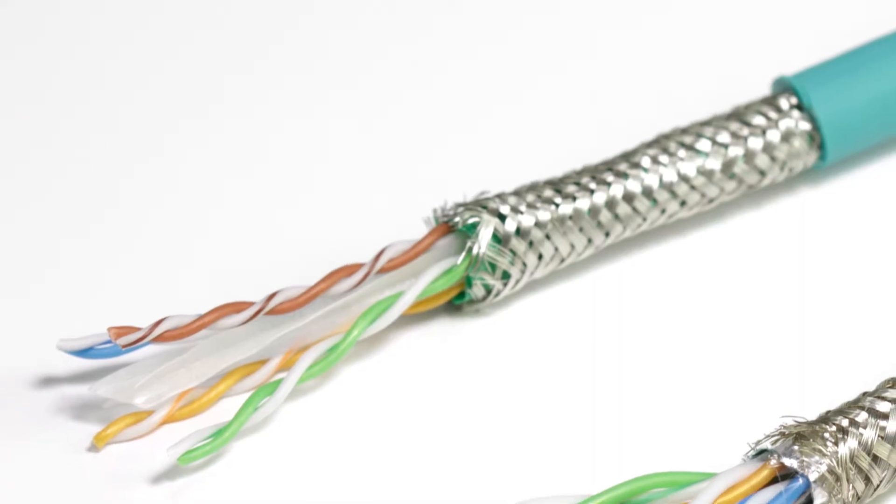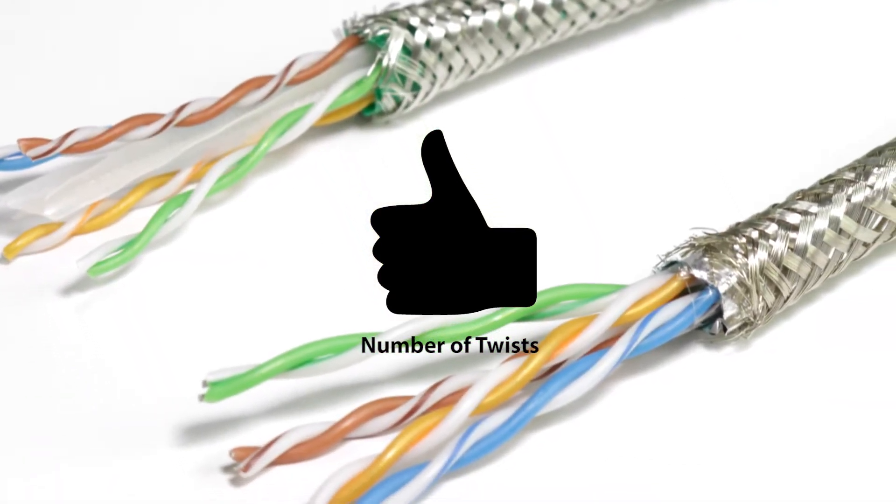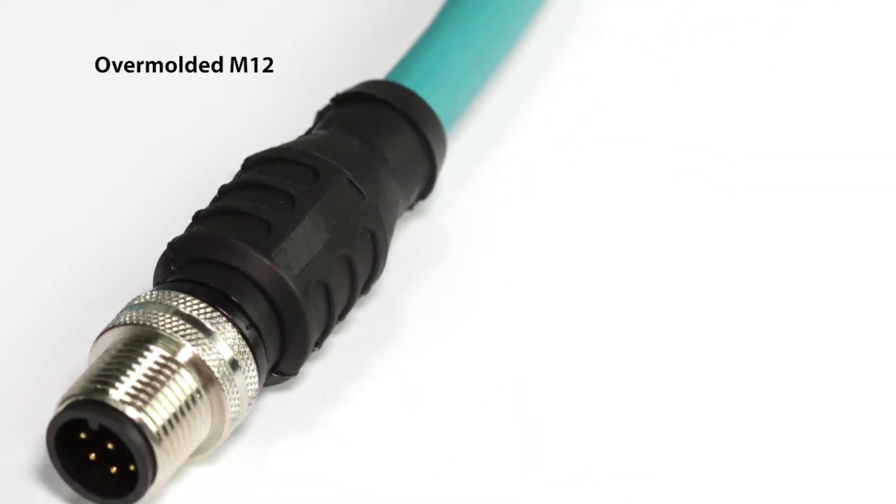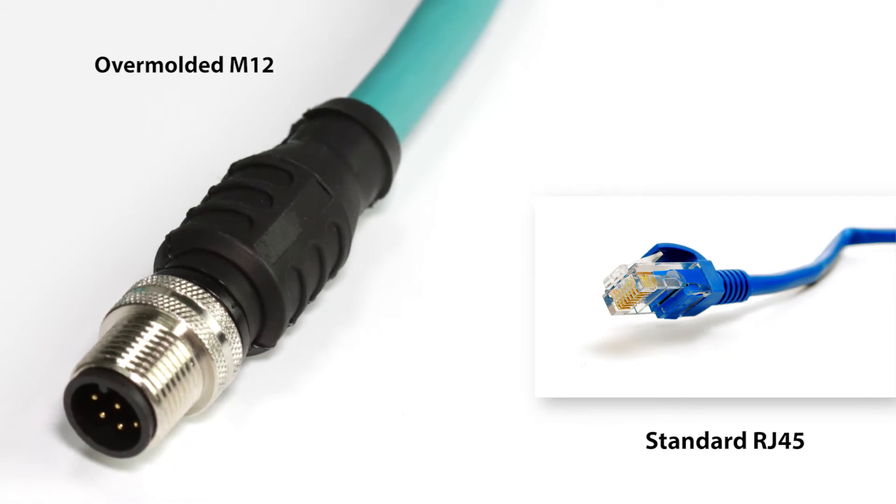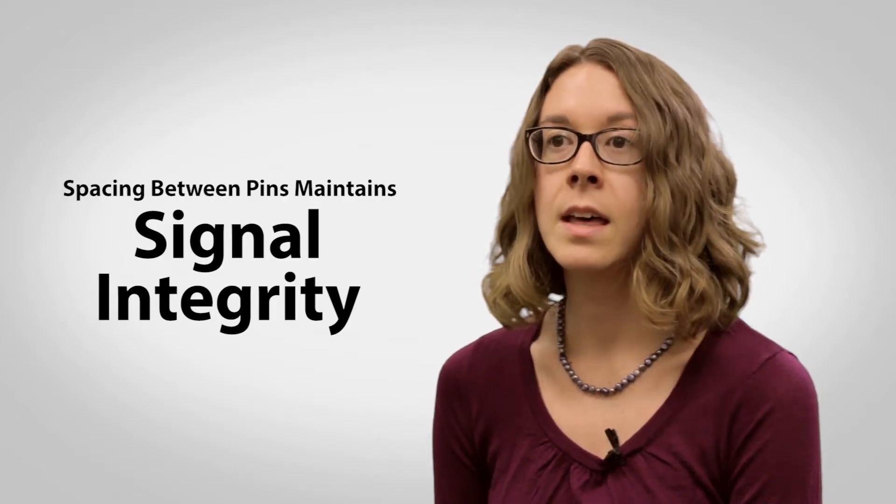For any Ethernet connector, the number of twists must remain at an acceptable level throughout the connector. An overmolded M12 is used for industrial Ethernet because it is considerably more robust and rugged than the RJ45. And the spacing between pins maintains signal integrity. This is what makes it ideal for the factory floor.